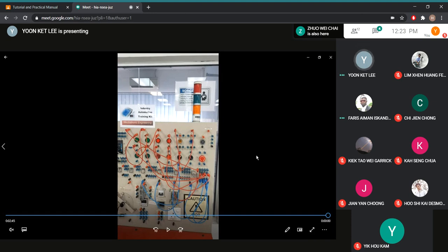So for example, with the retentive timer, today I start my machine for 2 seconds. Tomorrow I start my machine for 2 seconds. And the third day I start my machine for 1 second. If my preset value is 5 seconds, what will happen to the retentive timer? They will record 2 seconds for the first day, 2 seconds for the second day, and 1 second on the third day, then they will straight away turn on for 5 seconds.